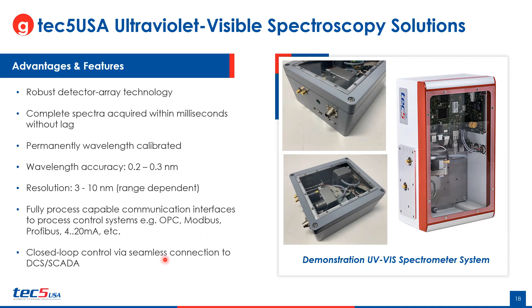These devices are fully process capable to any control system, whether it's a PLC or DCS. These examples include OPC, Modbus, Profibus, 4 to 20 milliamp, etc. And ultimately, these devices can be connected to your DCS or SCADA or PLC and introduce closed loop control so that you have automated feedback based on a result.